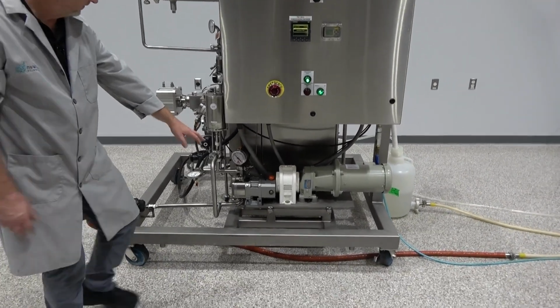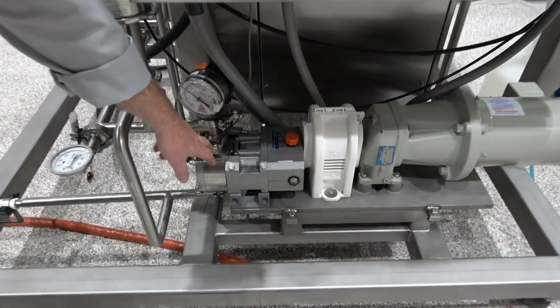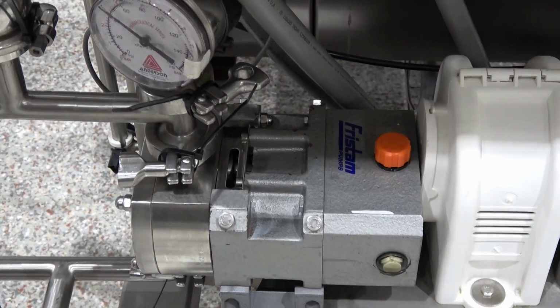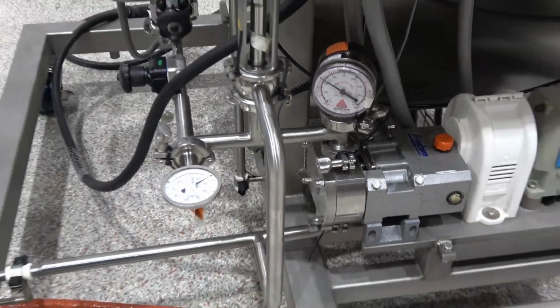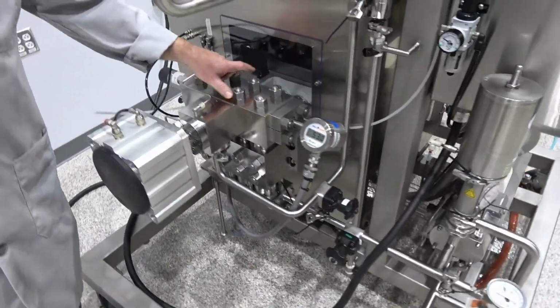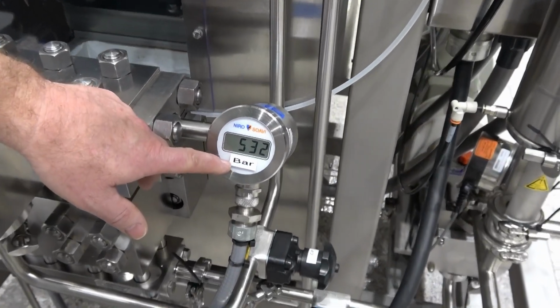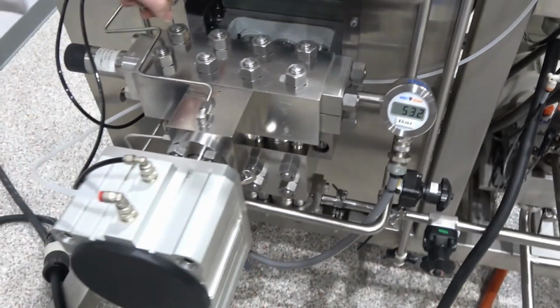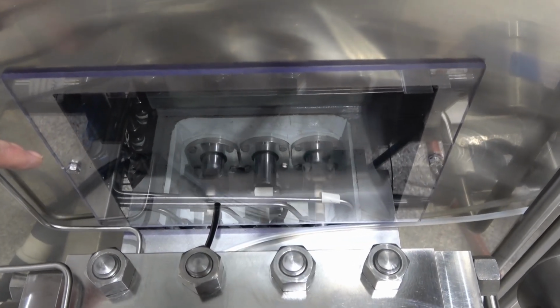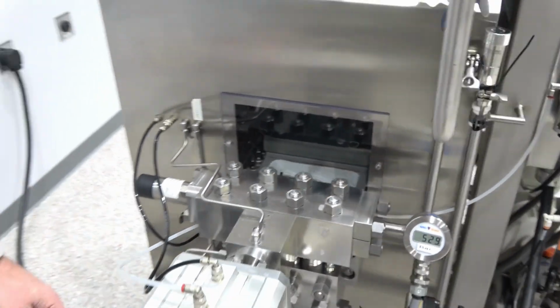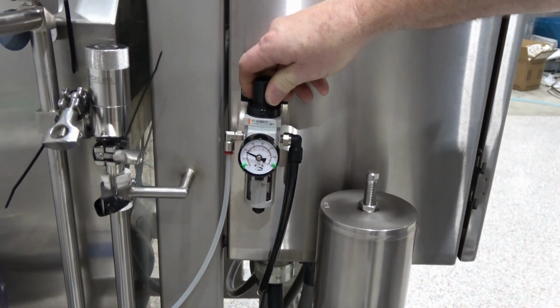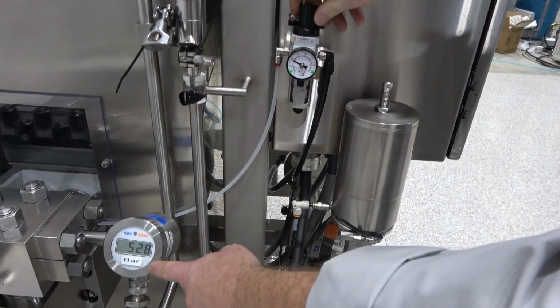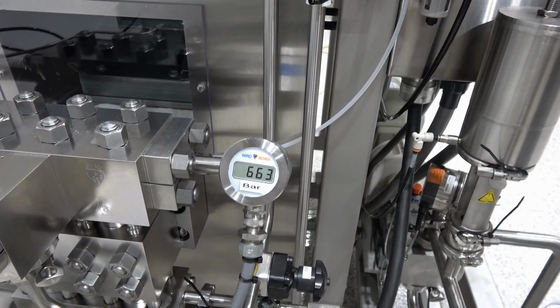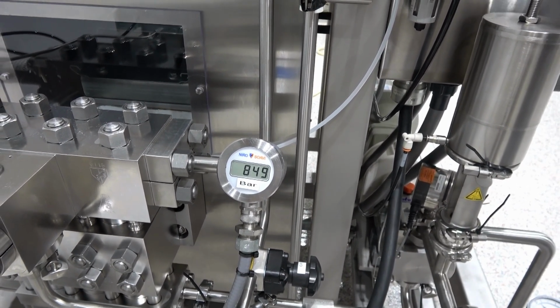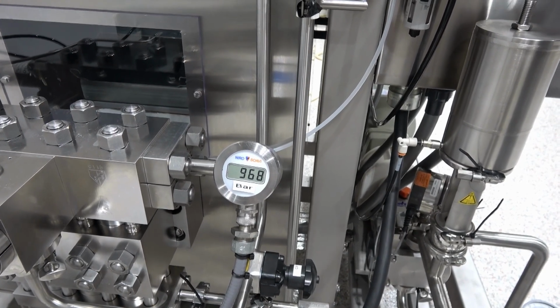So right now our first pump is running here. You can see it down in there. Got a 2-cylinder pump there. We got our pressures here. The fluid is coming through, and we know it's coming through because we're running at pretty high pressure right now, 530 bar. You can see our 3 ceramic cylinders pumping right here. And we're just going to show you what we did over here on our air regulator. So when we crank up the air here, we're going to raise the pressure down here, and you can see our pressure start raising up here. We're going to go ahead and go all the way to 1,000 bar, which is about 15,000 psi, I believe.